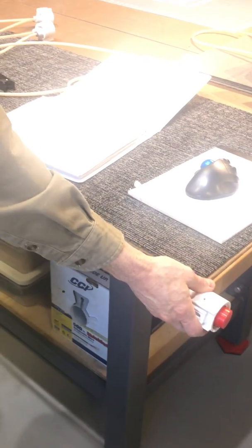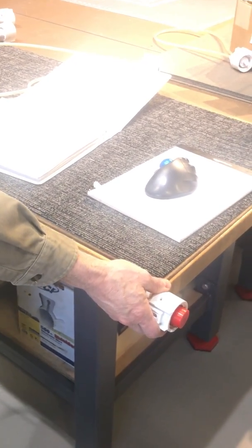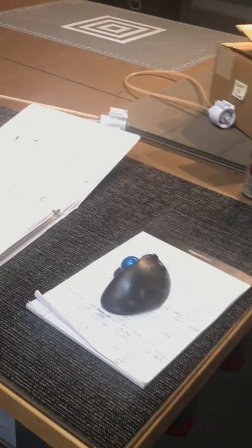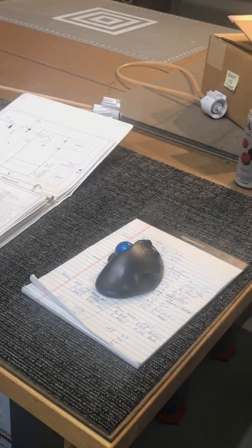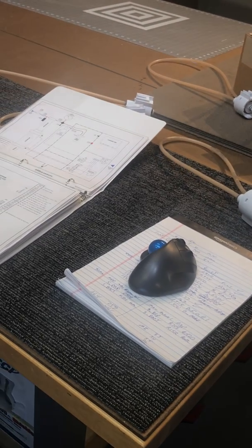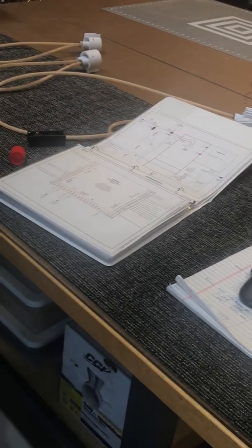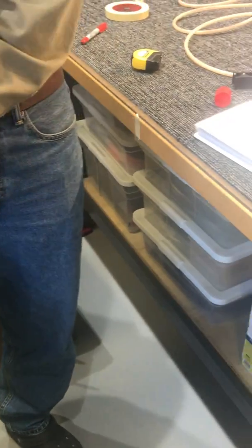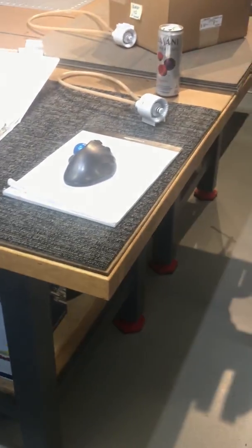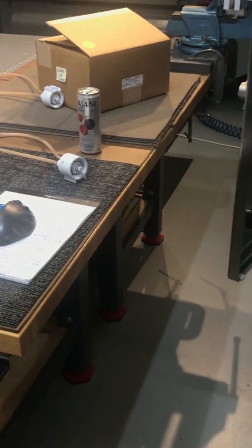I would like to see this. Normally speaking, nothing's going to happen to your parts. These parts are too good for this test. But if you're going to check this repeatedly, then don't kink the tubing like I did. But that didn't seem to matter though. I found that if you hold them at 1,000, it's going to go eventually. But when these tubes are slightly warmer, they may not kink as easily either. Although you're at 70 degrees in here, very close. 68, well, according to the cabinet.